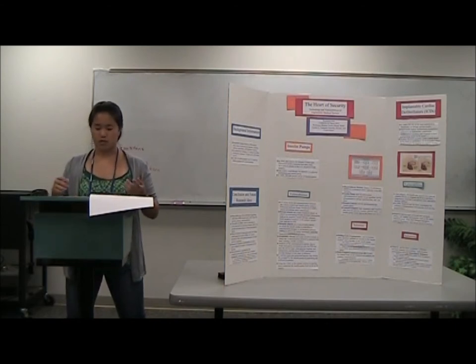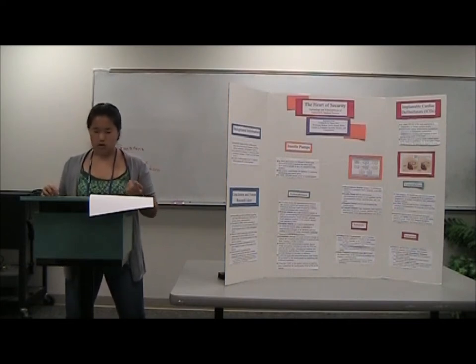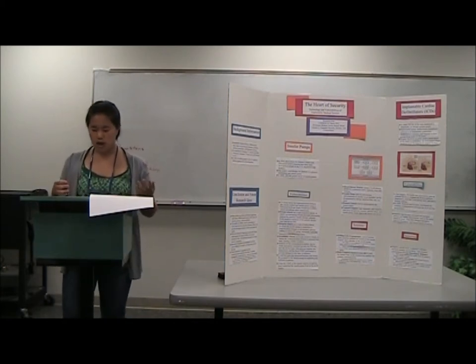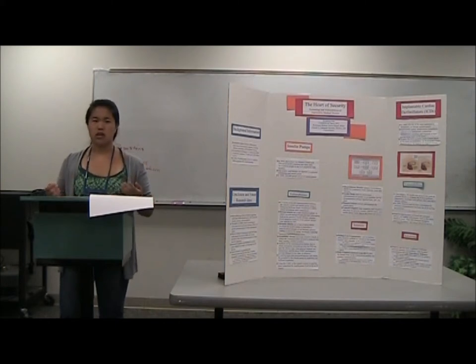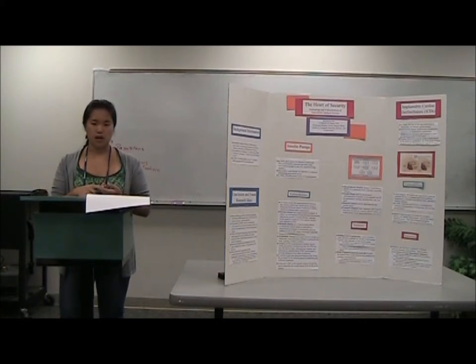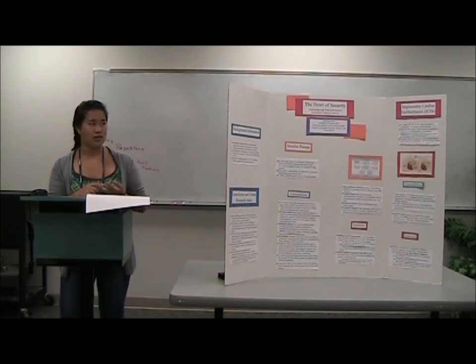The people who did the study were named Lee, and I'll just say Lee because the other two names are long. They used something called a universal software radio peripheral, which is a radio device used to eavesdrop on communications, especially wireless ones. And they found that they could intercept the radio communications between the remote control and the insulin pump. They also figured out that when they eavesdropped on the communication, most of the data was transmitted in plain text. The things that were transmitted included the device type, which buttons were pressed, whatever readings were transmitted, and more importantly, the device pin.